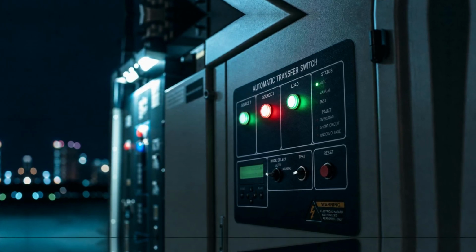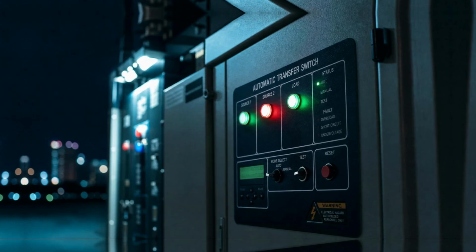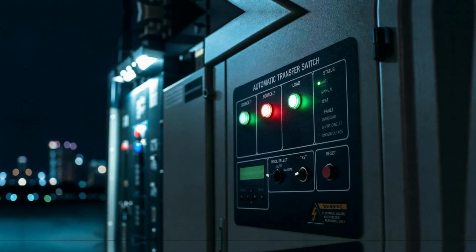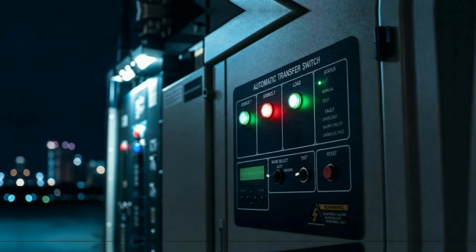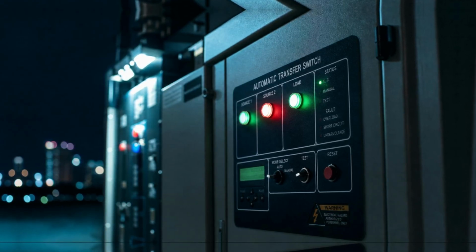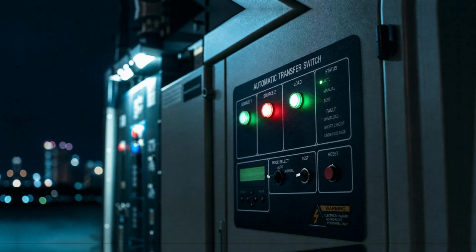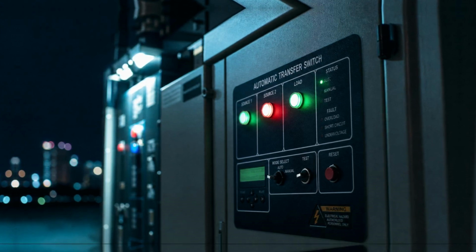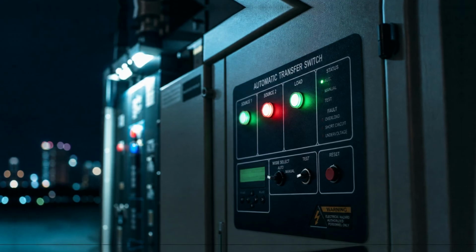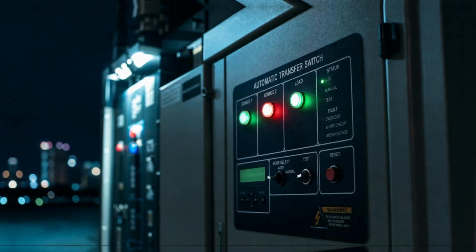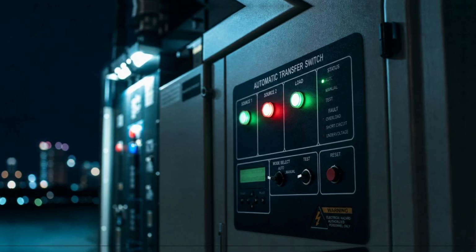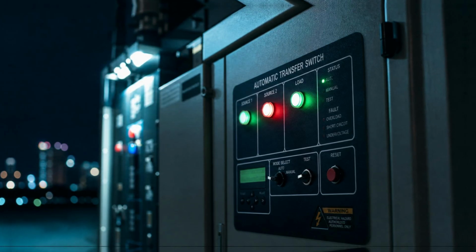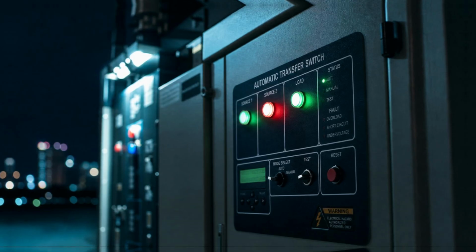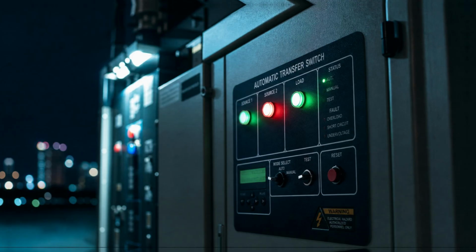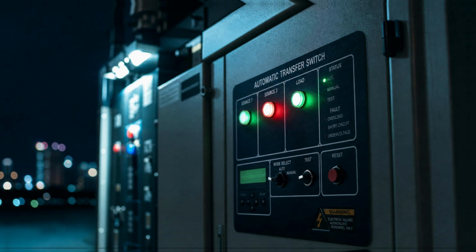Now, let us follow the start signal as it travels. Because while the transfer switch was receiving its instructions and preparing to act, another process was already beginning somewhere else in the building, or perhaps behind the building or beside it, in a structure purpose-built to house the machine that emergency power ultimately depends upon. The generator room, if there is one space in the entire emergency power infrastructure that earns the word room in the fullest sense, a space with presence, with weight, with a particular atmosphere that is unlike any other part of the building, it is the generator room.